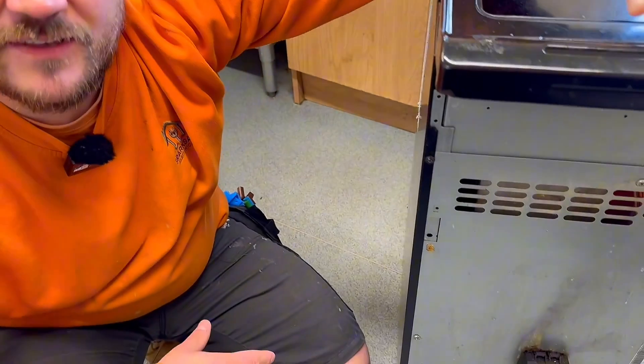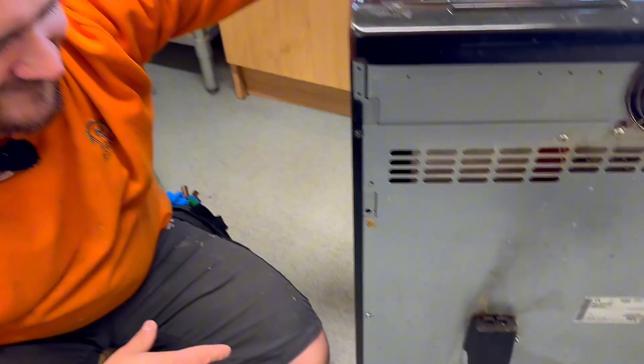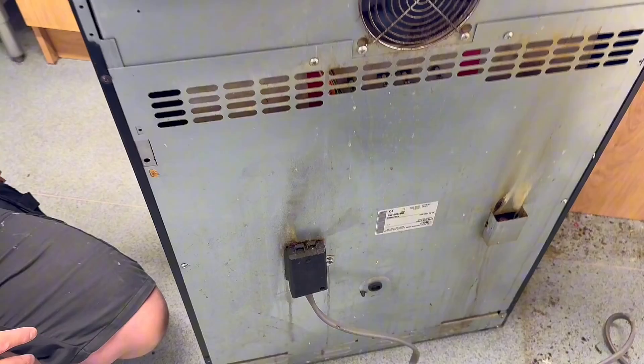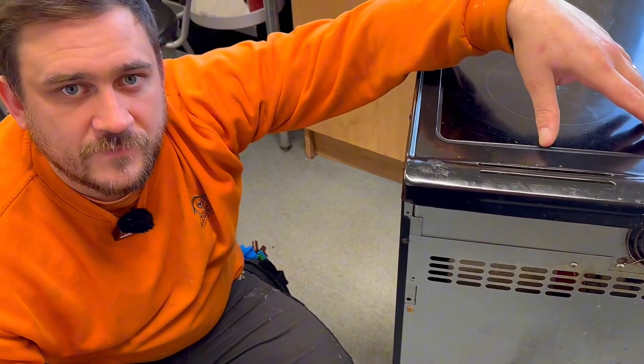I've got the absolute pleasure today because I'm out on site with my best mate Marcus and we're carrying out the EICR. We're going to be a little bit less controversial today as we look in the back of this oven here and describe how often we would carry out a test on this in an EICR to prove the exposed conductive part — the oven itself — is actually earthed.